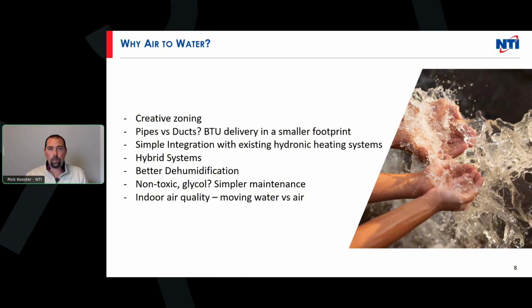And indoor air quality. Anytime you think about moving air versus moving water, right? We're not spreading germs, viruses, bacteria, all this stuff that may be airborne, with a hydronic system. We're moving water through a pipe, right? Whereas when you think about a centrally ducted system, we could be moving that air from room to room, especially with a central return. You're basically injecting everything in that space into the other rooms. So it's a lot easier to get sick. So better indoor air quality typically with water-based systems.